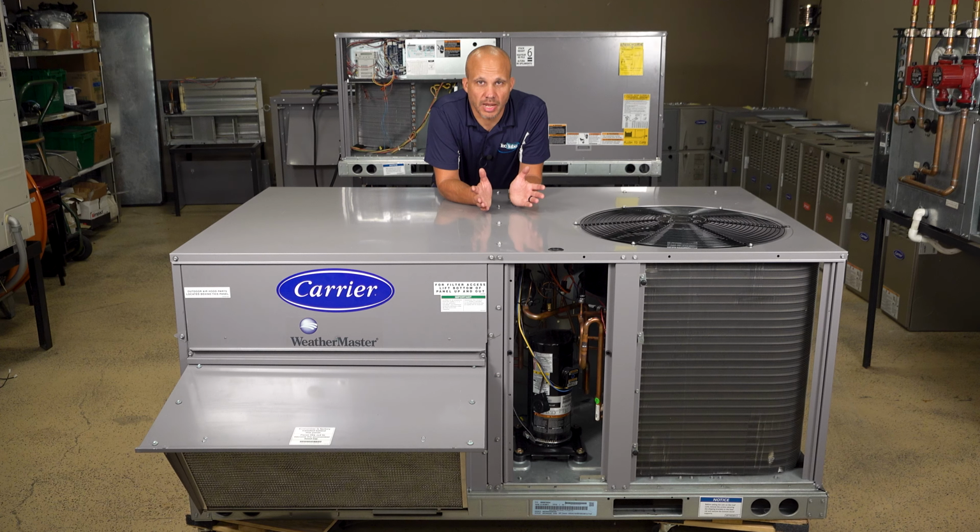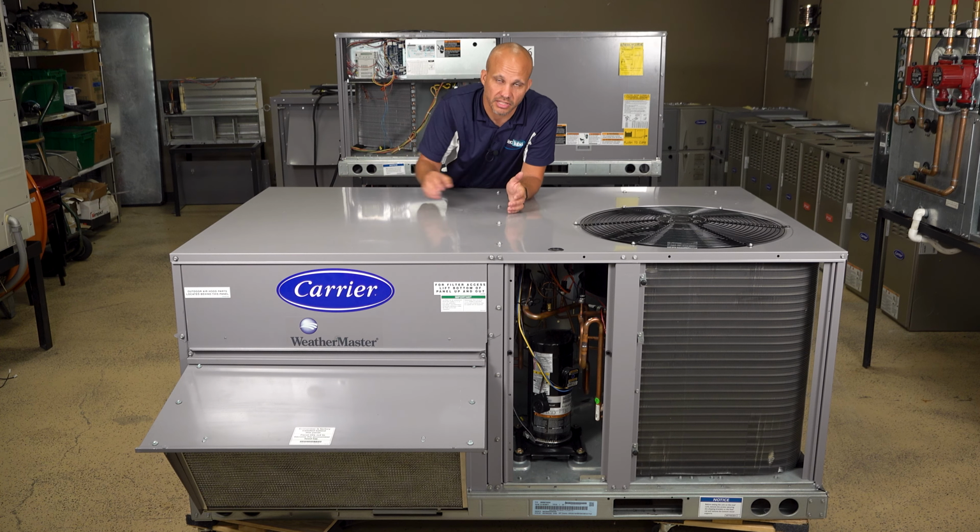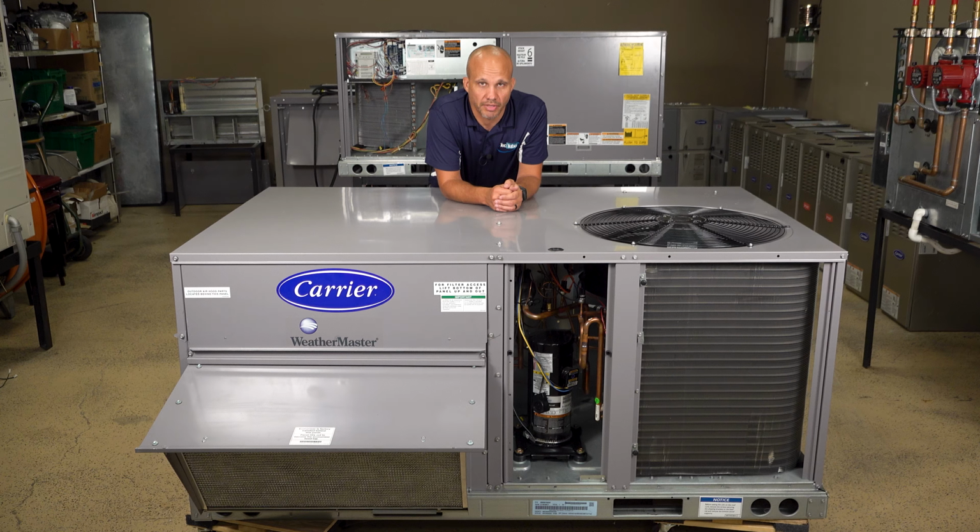So this will be our first example of a heat pump. This is a packaged rooftop unit. We're starting with this one because a little over 50% of commercial buildings are heated and cooled with packaged rooftop units. It's called the rooftop unit because normally it's mounted up on the roof. It could be mounted on the ground and ducted into the side of a building, but generally it's up on the roof. And it's packaged because everything is in this box. The heating, the cooling, the fan system, everything is in here. Nothing goes in the building other than ductwork and a thermostat.